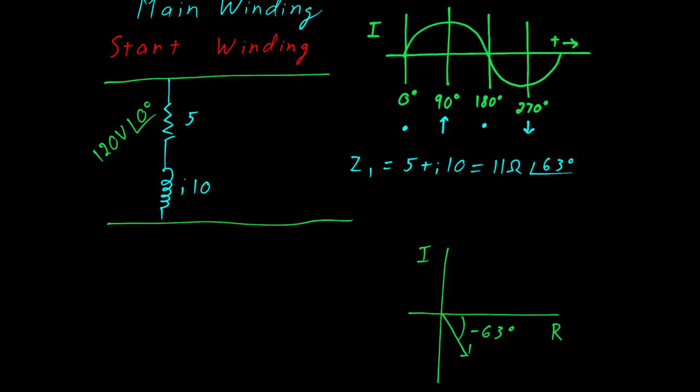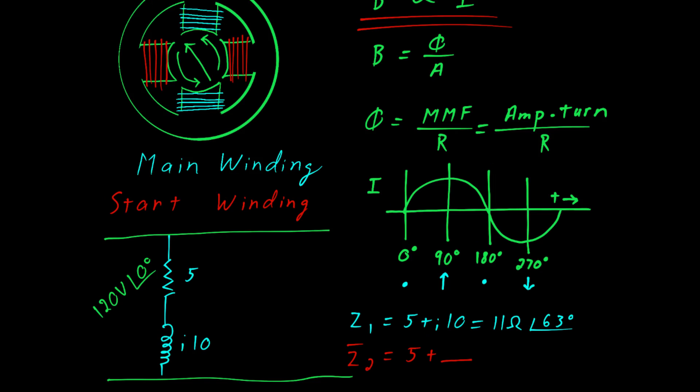Now when we added the start winding we know that we need to generate another current that is at a right angle to our main winding. We'll sketch that here as a current that has an angle of 27 degrees. For this discussion let's assume the start winding is identical to the main winding and both have a resistive component of 5 and an inductive component of J10. To change the phase angle of the current then we're going to need to add a capacitor. Again we want our impedance Z2 to be equal to 5 plus something such that that something is going to give us an angle of negative 27 degrees.